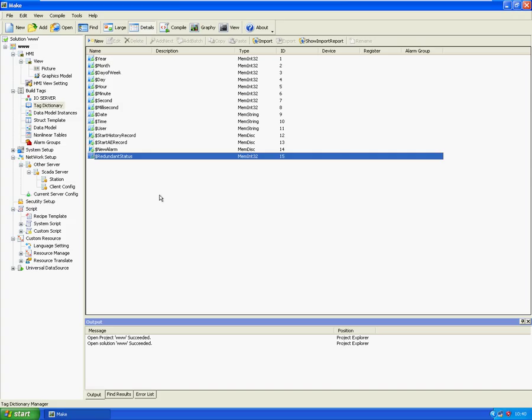Transform the status manually. In particular situations, you can modify the system variable redundant status by force to realize manual switch between the master machine and the slave machine. Switch to the slave machine. The value of system variable redundant status in the master machine is changed to 2 by force. The master machine lays off and stops responding to the slave machine query. It seems to the slave machine that the master machine is broken.